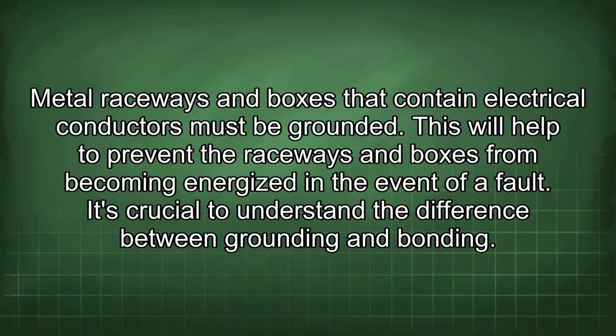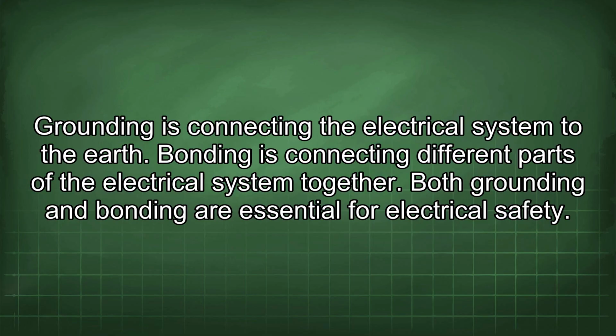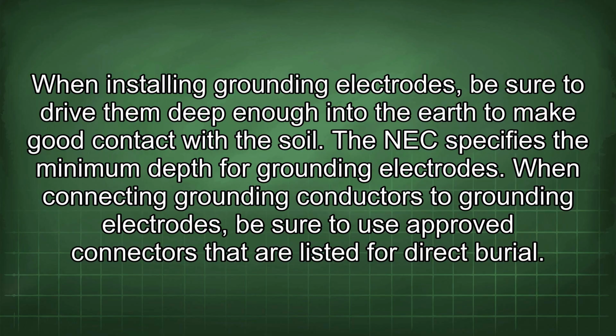It's crucial to understand the difference between grounding and bonding. Grounding is connecting the electrical system to the earth. Bonding is connecting different parts of the electrical system together. Both grounding and bonding are essential for electrical safety. When installing grounding electrodes, be sure to drive them deep enough into the earth to make good contact with the soil. The NEC specifies the minimum depth for grounding electrodes.